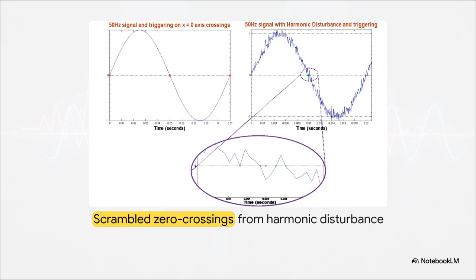On the left, you've got this beautiful, smooth sine wave cleanly crossing the zero axis. But on the right, look at those jagged, noisy lines. That's what harmonic disturbance does to a voltage waveform. If you zoom in on that purple circle, you see a massive problem: instead of crossing the zero line exactly once, that jagged noise causes the signal to cross it multiple times in just a fraction of a millisecond.